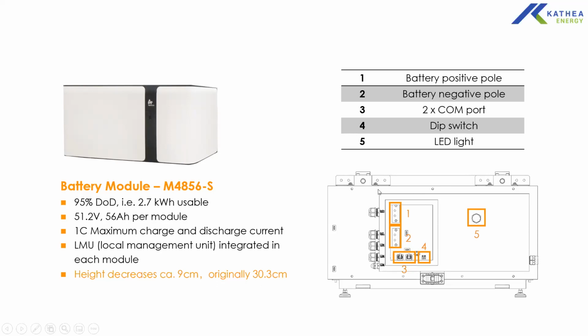You would have dip switches. So when you set up your battery, depending on the configuration or how many batteries you have, you need to set your dip switches in a digital format for each and every battery from number 1 to number 8. The dip switch setup is covered in the installer manual. And then the battery has an LED indication which comes on when the battery is in operation mode, and when it's off, it means the battery management system is actually off. The ring is green, flickering, but when it illuminates red, it means the battery has a fault, and you need to refer to the monitoring portal or the screen on the HV box to see what the fault is.